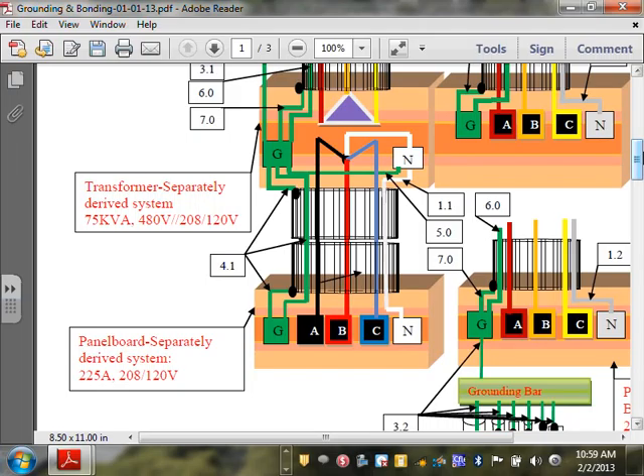They discovered, at least based on a book I read, that these fittings that are not bonded properly will burn. What's wrong with them burning? They could be a fire hazard under a ground fault condition. Now, could it happen? You could go 50 years and it never happens, right? That's the problem when we size systems, guys, we size it based on a scenario that could never happen. But we do it anyway because we size based on our scenario.